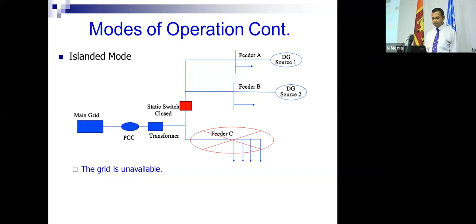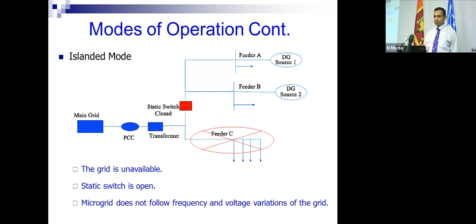When the grid is not available, we call it an island situation. During that time the grid is not available, the switch is open, and the microgrid does not follow the frequency and voltage variation of the grid. The main problem is that even though the system is not connected to the grid, you still have to control the voltage and frequency. So your microgrid should have the capability to control them, and that part is done by the microgrid central control.